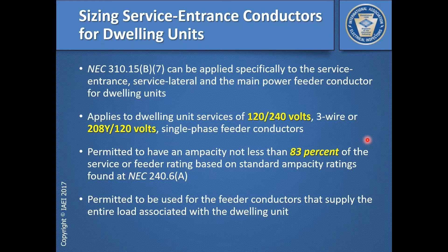If you went to table 310.15(B)(16) and looked at 2 AWG or 3 AWG copper, even in the 90-degree column, it would tell you that a 2/0 AWG copper conductor is only good for 130 amperes.